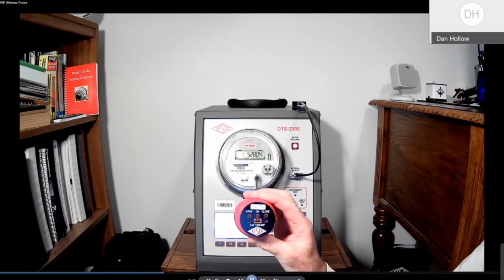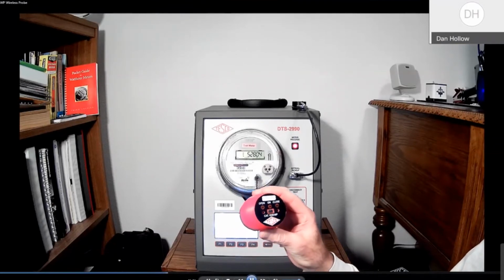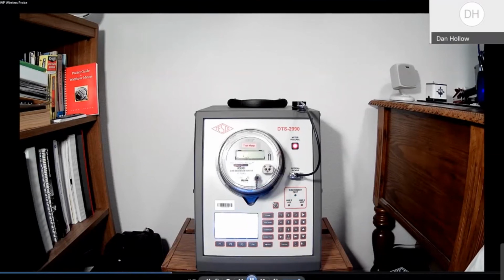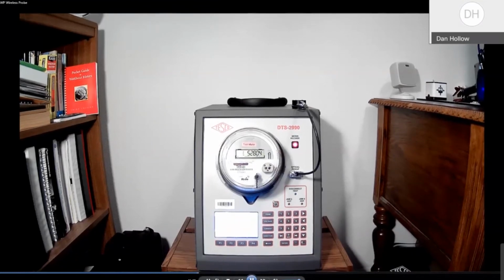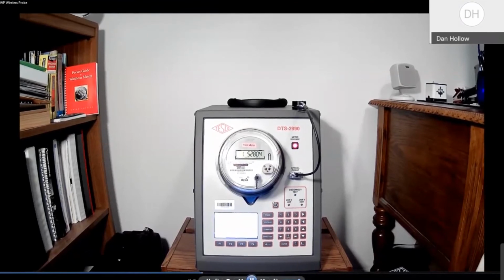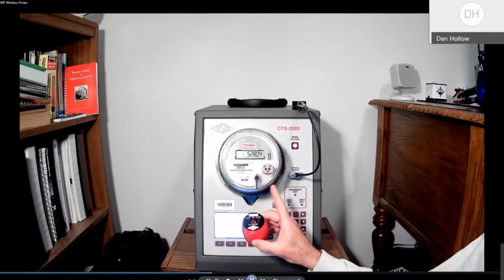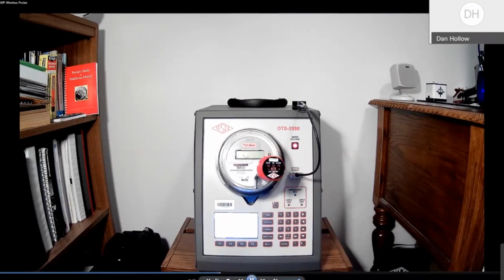It is not Bluetooth. It is a radio device and has a range of 1,200 feet and uses this little radio, USB. Looks like a USB stick, memory stick, but it's not. It's a radio. So I'm going to plug that into my laptop, which will stay back in your truck. And then this particular meter has a demand reset switch that's very close to the optical port. It will stay on there and it will communicate.